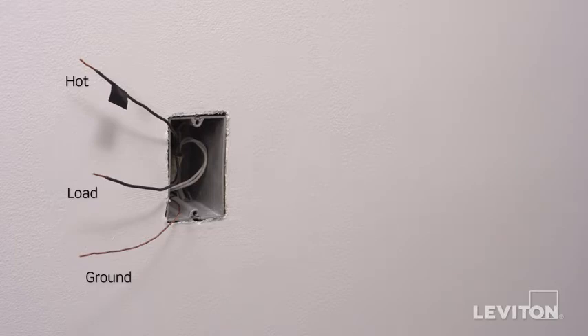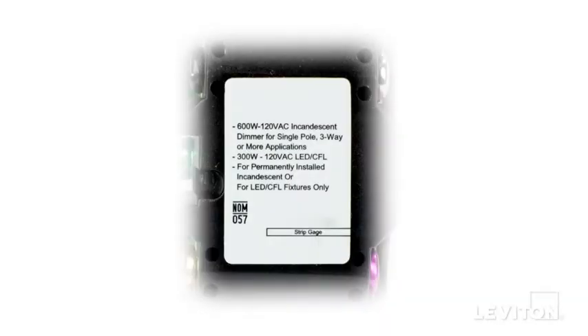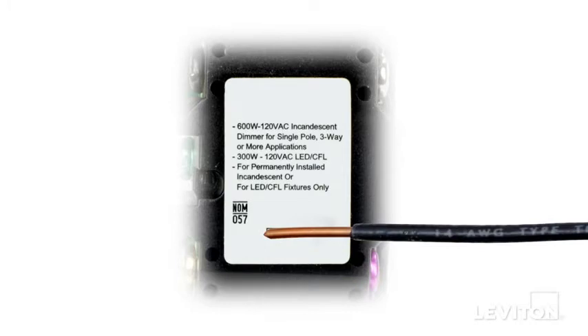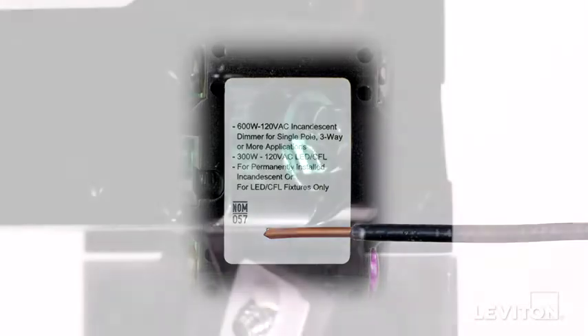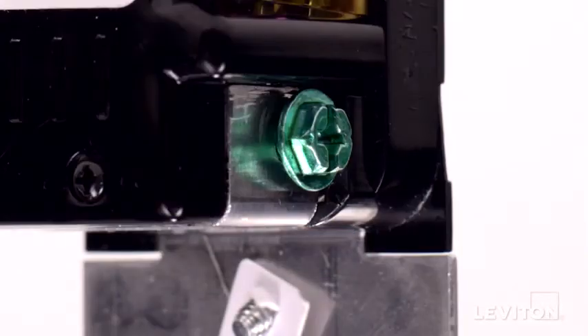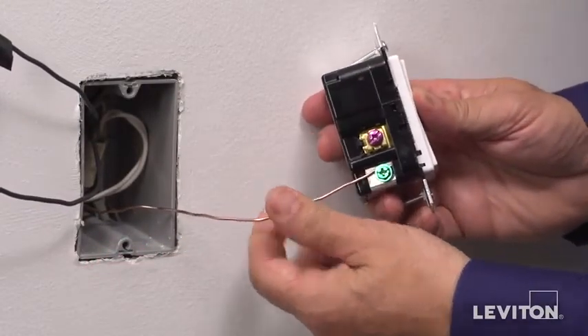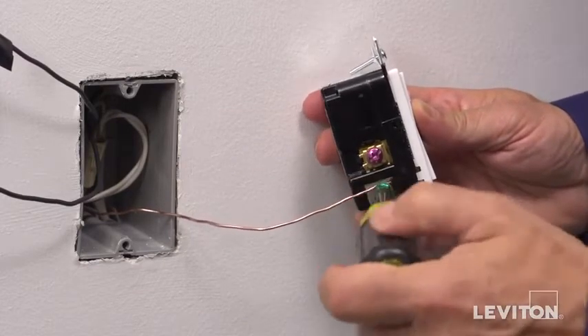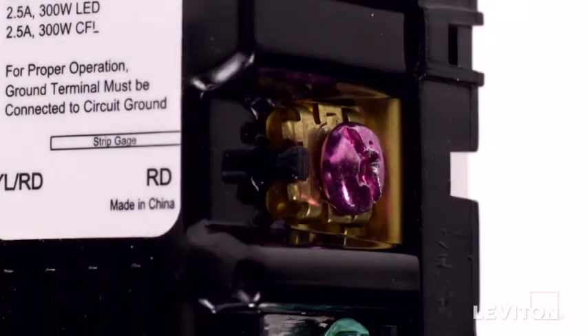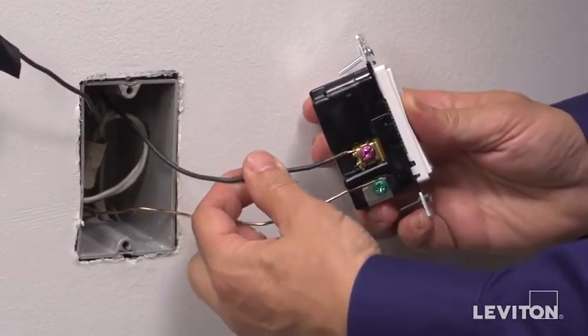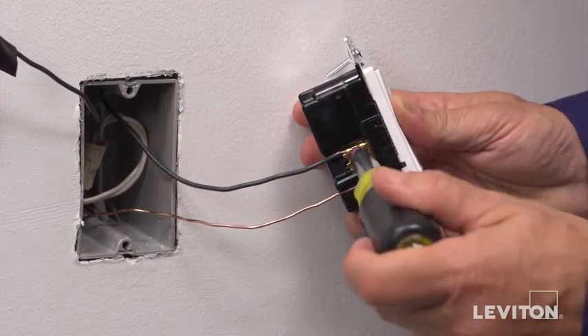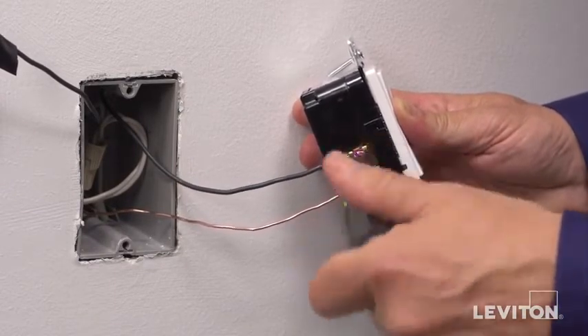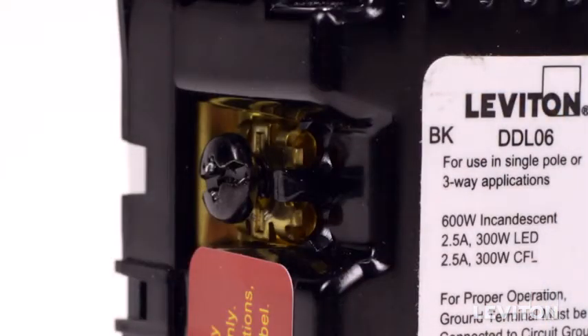Next, you need to be sure that the wires are prepared for installation. Start by making sure the wires are straight and stripped according to the strip gauge located on the back of the device. To wire, connect the green or bare copper wall box wire to the terminal screw marked GR. Connect the load wall box wire to the terminal screw marked RD. Connect the line or hot wall box wire to the terminal screw marked BK.